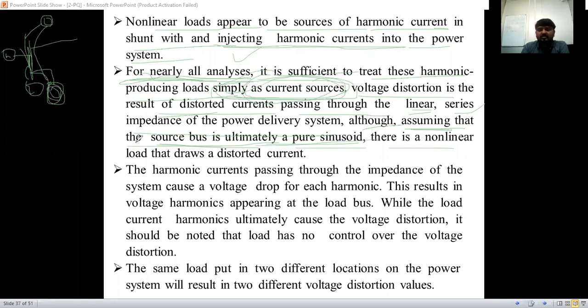Why is it pure sinusoidal? Because the non-linear load draws the distorted current. The harmonic currents pass through the impedance of the system, and that causes a voltage drop for each harmonic, first harmonic, second harmonic, and for each half cycle where harmonics are there. So the harmonic currents passing through the impedance of the system cause a voltage drop for each harmonic.